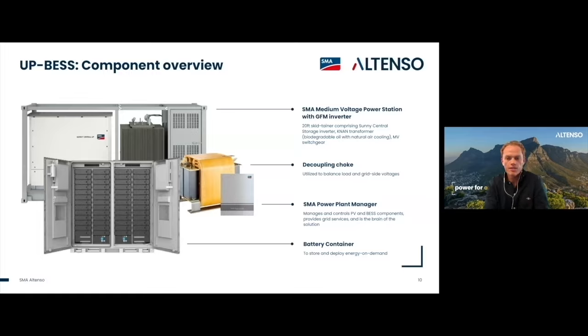And then you would also have a decoupling choke, which essentially acts as a coil or single-phase transformer and is able to sustain the voltage at the point of interconnection in the event of a grid disturbance fault. And of course, you'd need your battery container from the likes of CATL, BYD, and others that we work with. And the benefit of working with Altenso is that we're a one-stop shop for all of these components. So you would be working with us directly, and we're also able to work on the overarching energy management system required using the power plant manager at its core.